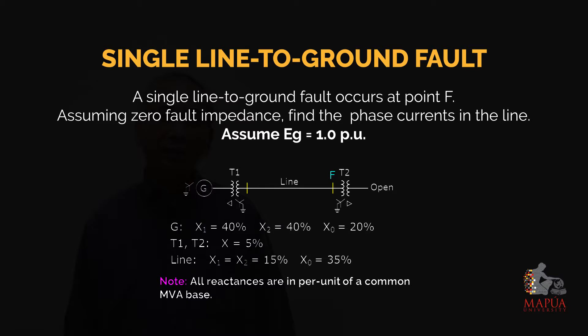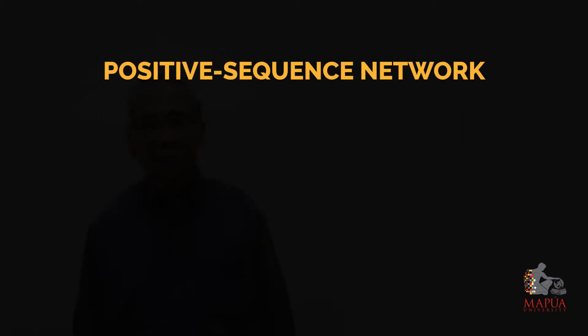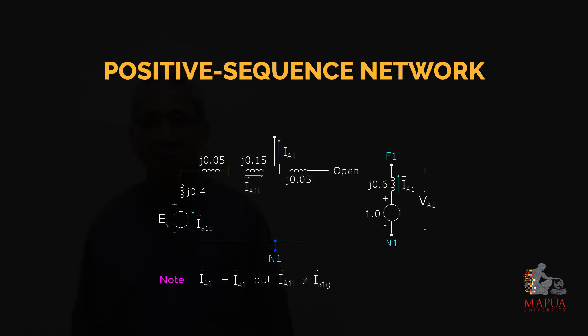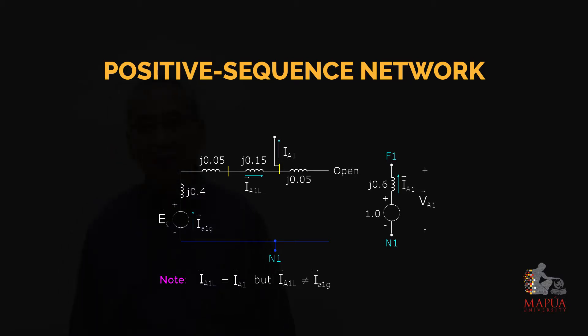Considering the location of the faulted point, we can now redraw the positive sequence network following the one-line diagram. This represents the positive sequence network with the positive sequence reactances, the generator, and the location of the faulted point, called F1. This positive sequence network can be represented by an equivalent Thevenin circuit with terminal F1 and neutral reference N1, a generator value of 1 per unit, and j0.6 as the sum of all impedances in the positive sequence network.